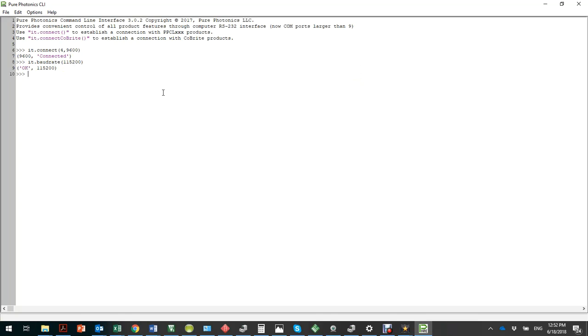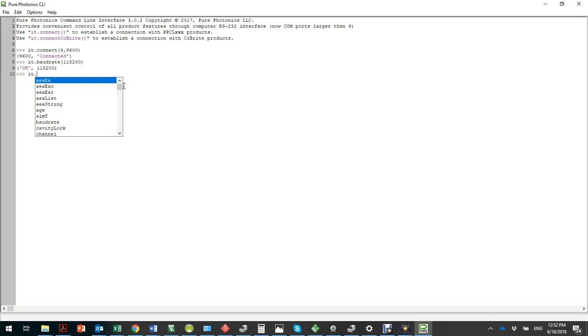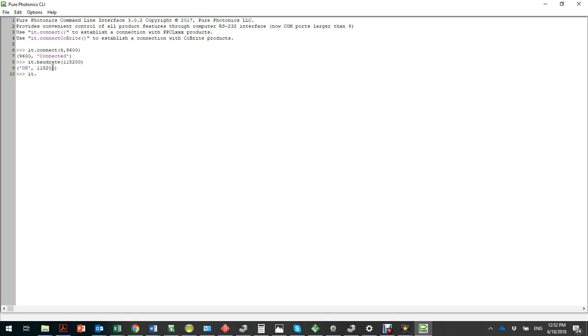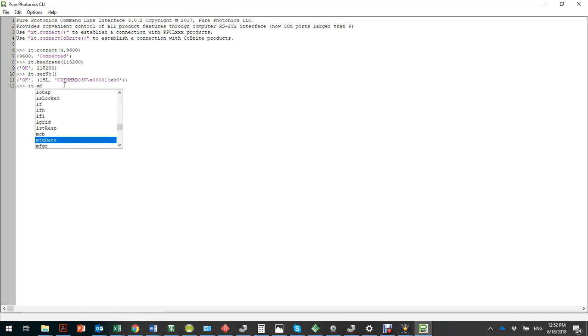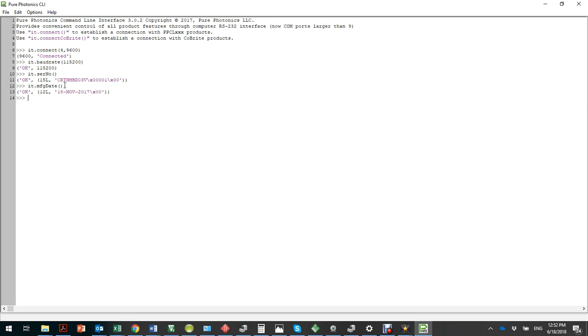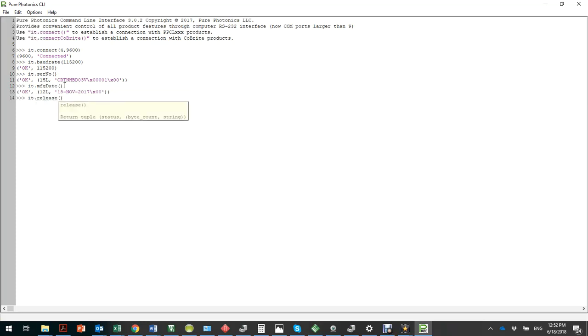As you can see, we communicate to the laser through commands — it.dot and then all of the commands are listed here. For example we can use laser commands. We can get unit parameters. We can get the serial number — for example this is CRTN HBD03V. We can get the manufacturing date. We can get the firmware version — 8.0.9 in this case.